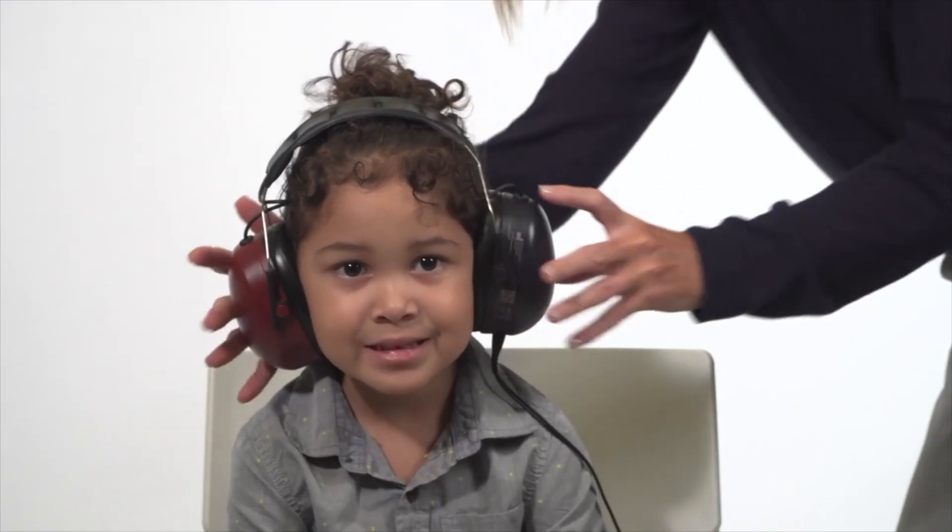Place the headphones directly over the subject's ears with the red phone on the right ear and the blue on the left. Remove any obstruction that may interfere or be uncomfortable, such as glasses. Adjust the headband so the headphones are centered over the ear canal.